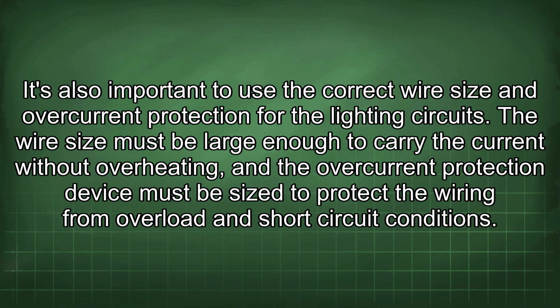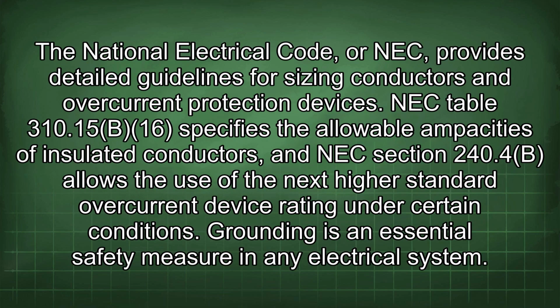It's also important to use the correct wire size and overcurrent protection for the lighting circuits. The wire size must be large enough to carry the current without overheating, and the overcurrent protection device must be sized to protect the wiring from overload and short-circuit conditions. The National Electrical Code, or NEC, provides detailed guidelines for sizing conductors and overcurrent protection devices. NEC Table 310.15(B)(16) specifies the allowable ampacities of insulated conductors, and NEC Section 240.4(B) allows the use of the next highest standard overcurrent device rating under certain conditions.